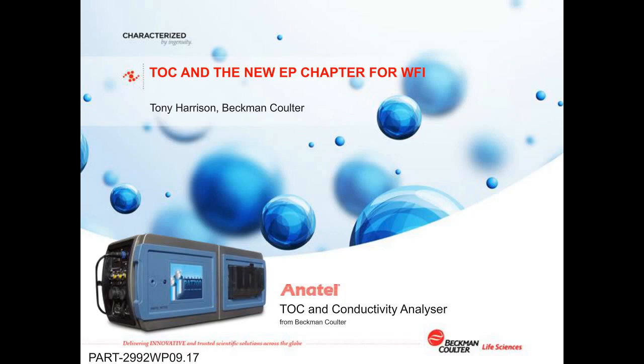Thank you for that. Our next question is, if the Pharmacopoeias mandate the system suitability test as a requirement for TOC analyzers, why is a separate calibration procedure required? Yeah, it's a good question, and often system suitability confuses people. In fact, system suitability is not a calibration. It merely establishes that the TOC analyzer is capable of oxidizing the relatively difficult to oxidize substance benzoquinone, as well as it can oxidize the more easily oxidized sucrose.